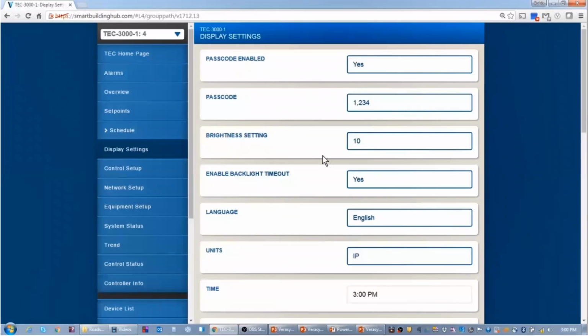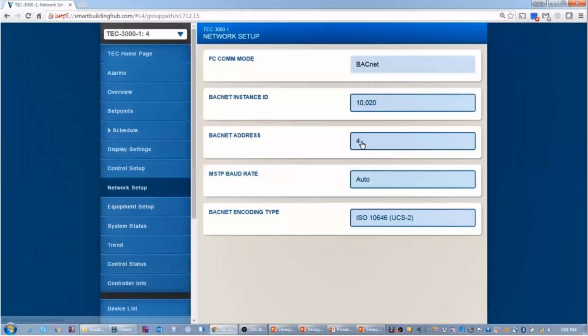So really, the best way to describe smart equipment: as I mentioned earlier, in the Niagara supervisor environment you have to map each point and give it an address on the network. But with plug and play here in Verasys, you can simply go to the network setup and change the BACnet address—for example, from 4 to 5.